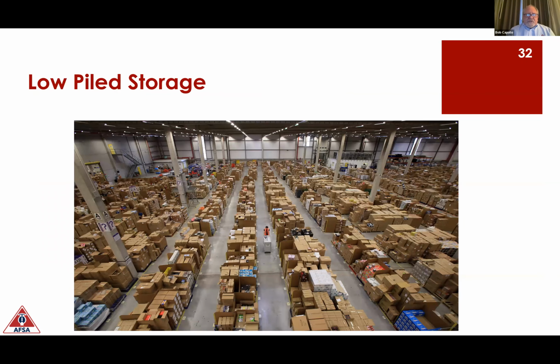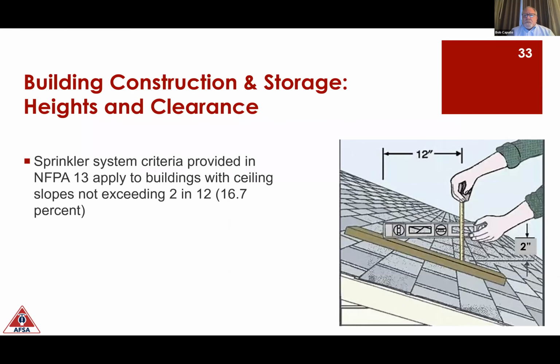We also have what's called low piled storage as opposed to high piled storage, and that's a little more forgiving in terms of the fact that we have lower storage, so we're not going to have that fire climbing up very rapidly. But again, now I am going to delay the activation of the sprinklers because there's so much volume of space for the heat to get to the ceiling and open the sprinklers directly above the fire.